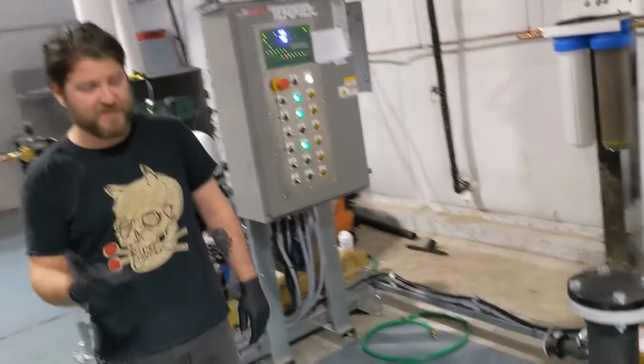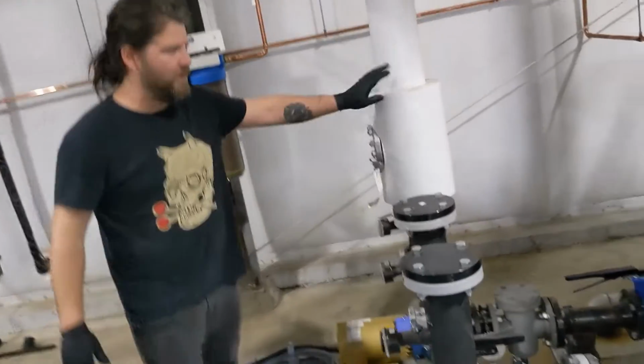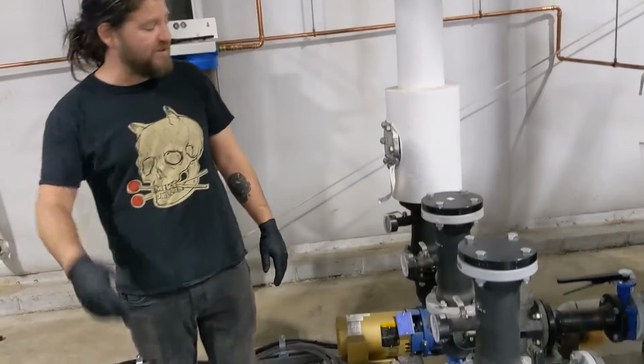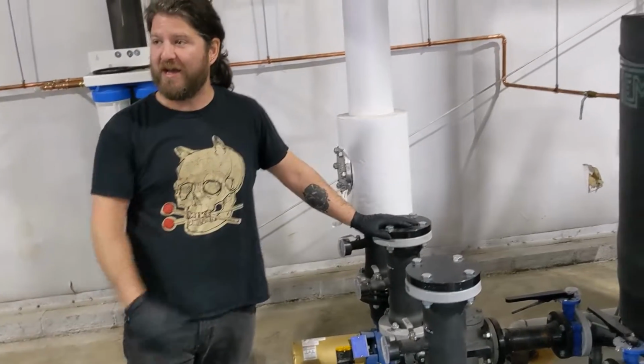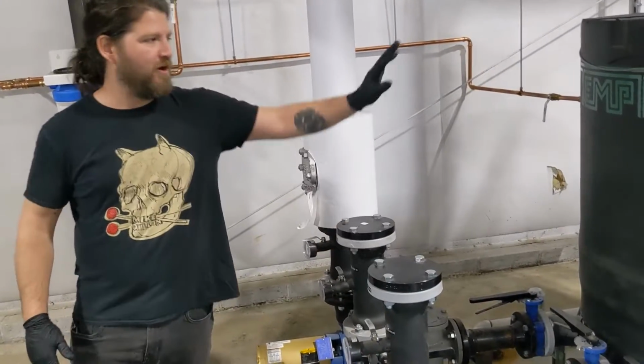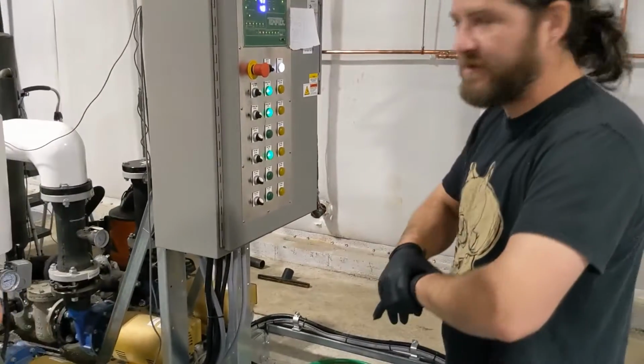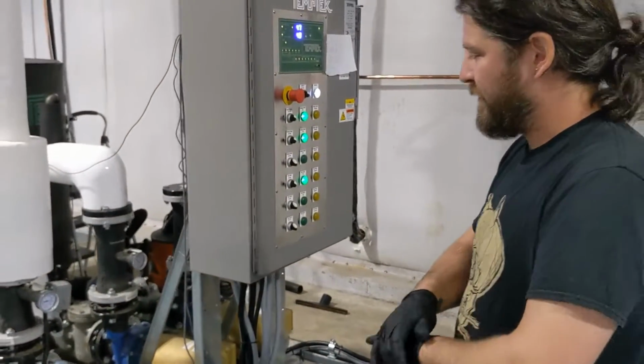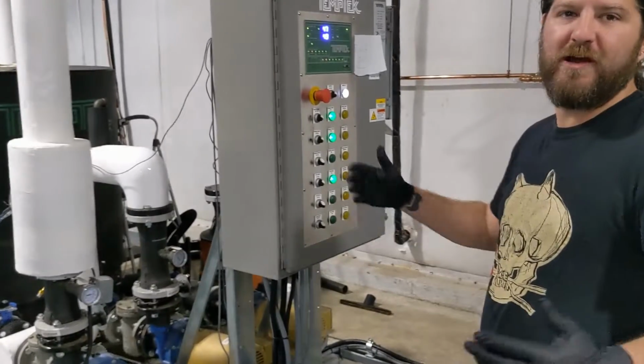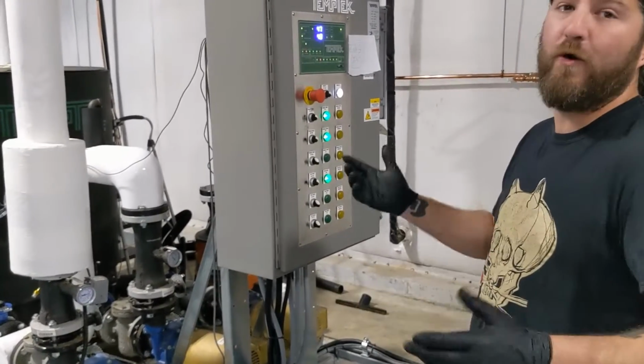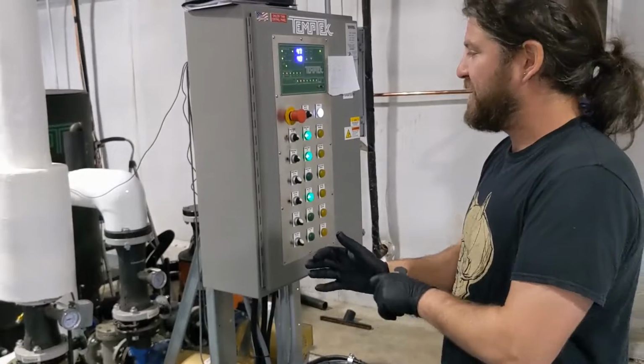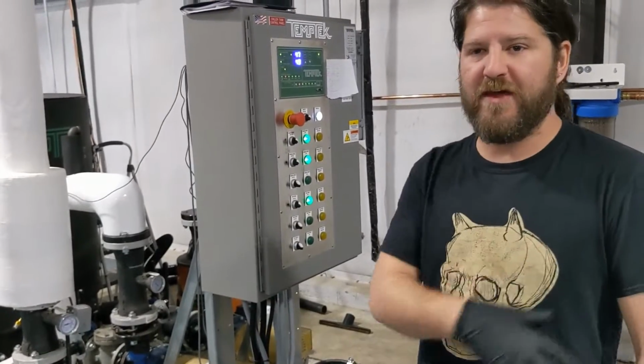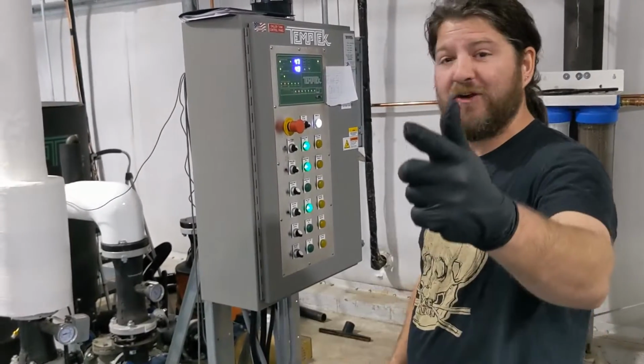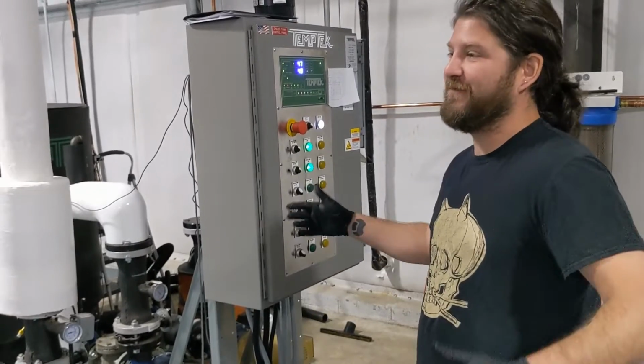So this is set up for 6 presses in the future, so we're only running one of these right now. Every 2 presses we add, we'll have to add another chiller outside and another pump. All of our tanks and everything are sized for 6 presses. And you have room to grow. That's cool, rather than shutting down in the middle of operations for however long. We did some pre-planning with power in this, but every 2 presses we have to add another boiler. Wow, it's very, very big.